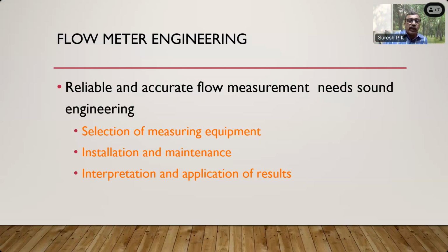Say, for example, positive displacement flow meters: you have air removers upstream of the meter, which remove the air and then send the fluid to the positive displacement meter. For turbine flow meters and DP meters, the standard says 20D upstream, 10D downstream. What is this 20D? 20D is 20 diameters of the pipeline, and 10D is 10 diameters of the pipeline. The standard says 20D, 10D, so you apply 20D, 10D.